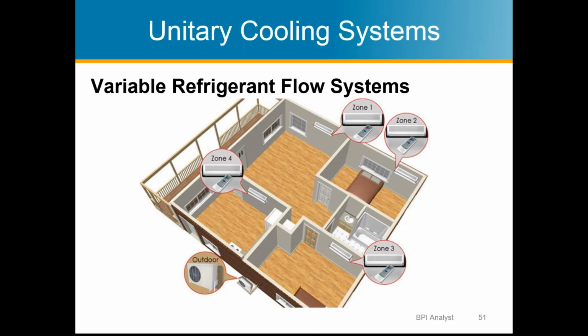Well, I guess most multifamily properties are still going to have unitary cooling systems, the cooling system types we've just talked about. So that filter is just going to be filtering the air in that one unit. Each unit would have its own filter and its own complete system. Ideally, the systems are designed for a certain MERV, and maybe for that reason, multifamily could potentially be easier because they're all going to be designed for the same MERV filter, and your multifamily property owner hopefully is going to be changing those filters themselves so that they can always get the right one in the unit. So maybe picking the right MERV is even easier in a multifamily unless there's something the person was asking about specifically that I'm not aware of.